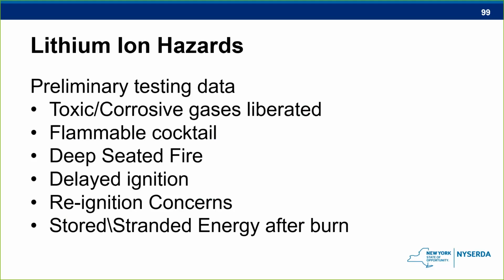What we also learned in this testing data was reignition. And this has happened quite frequently, and it goes back to, again, the codes and what the code officials are asking for. Reignition is a very real concern with lithium ion. So when these things go on fire and the firefighters will put them out, or the suppression systems may put them out or manage them and extinguish these things, there's a good chance that these things will go back on fire within a 24-hour period. And there was one test that was done where the battery was put out with a hose line, and this was in the testing lab, just so you know. It was put out with a hose line, and it went on 9 times in that 24-hour period.